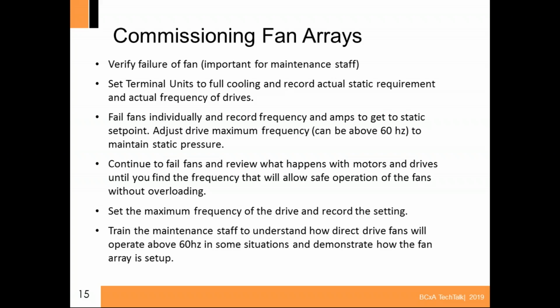I adjusted the drive to the frequency that it's supposed to be on the schedule, and I go into actually programming the drive to 60 hertz. And sometimes it can be above 60 hertz. And then what I'll do is I'll start failing the fans individually. And I'll fail, let's say in a 4-fan fan wall, I'll fail 1 fan. And the other 3 fans will ramp up and try to get to the set point. And then what I'll do is I'll record those settings.